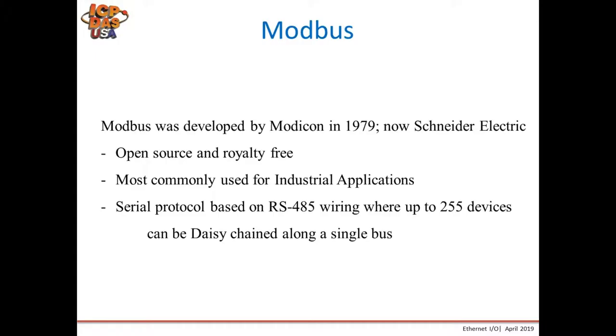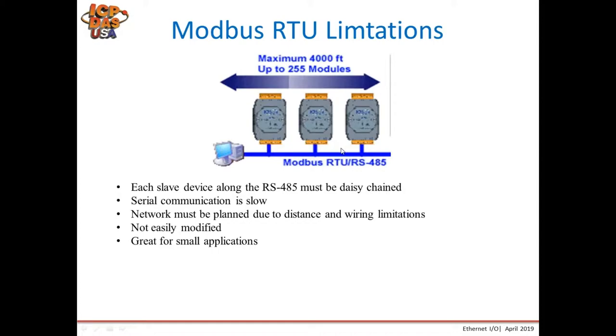Modbus was developed by Modicon in 1979, which is now owned by Schneider Electric. Modbus is open source and royalty-free and is the most commonly used industrial protocol. It's a serial-based protocol using RS-485 traditionally, and you can connect up to 255 devices along a single bus. Modbus RTU has limitations because each slave device along the RS-485 must be daisy-chained, serial communication is slow, and networks must be planned due to distance and wiring limitations. This is great for small applications, but for larger applications the distance limitation and single-bus daisy-chain can sometimes be a problem.